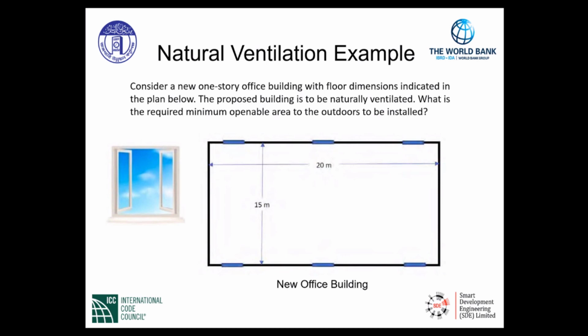Let's talk about an example of how to provide this natural ventilation. Consider a new one-story office building with floor dimensions indicated in the plan below. The proposed building is to be naturally ventilated. What is the required minimum openable area to the outdoors to be installed? As shown here, it's a smaller building, a new office building. The dimensions, as indicated here, are 20 meter by 15 meter. The natural ventilation will be through openings such as windows, indicated as seen here on the exterior wall. These are openable windows.